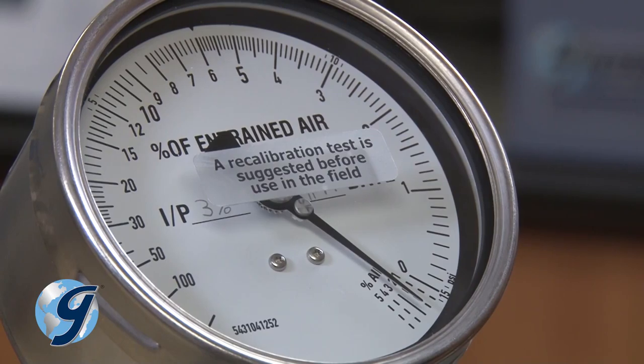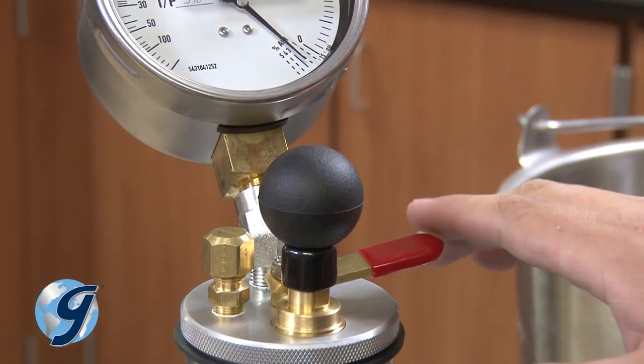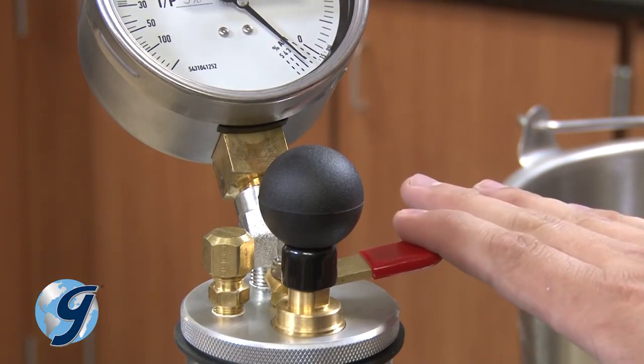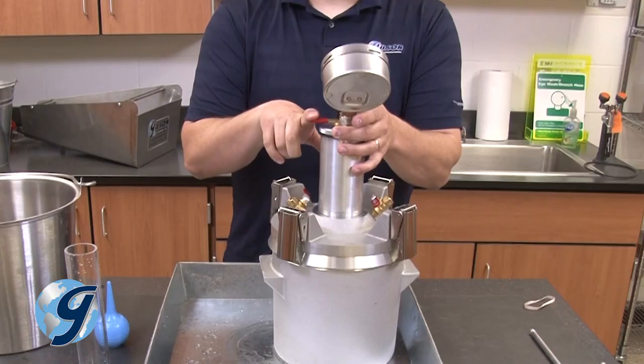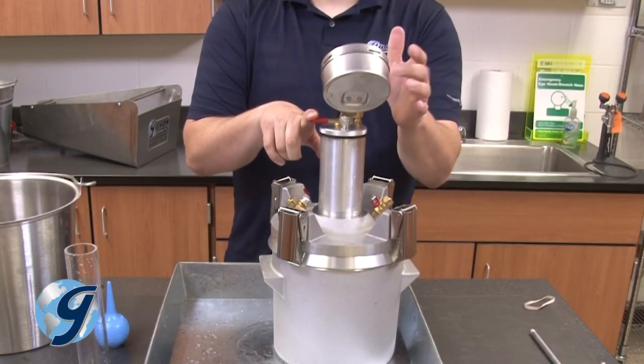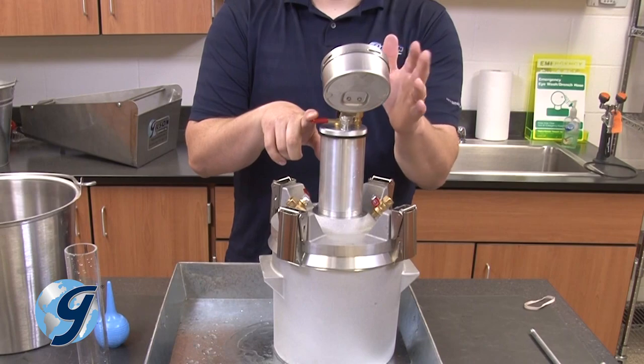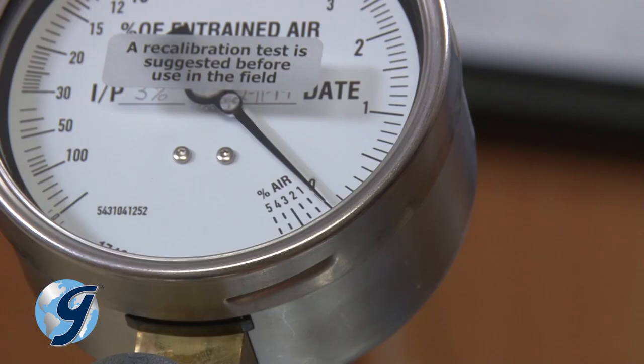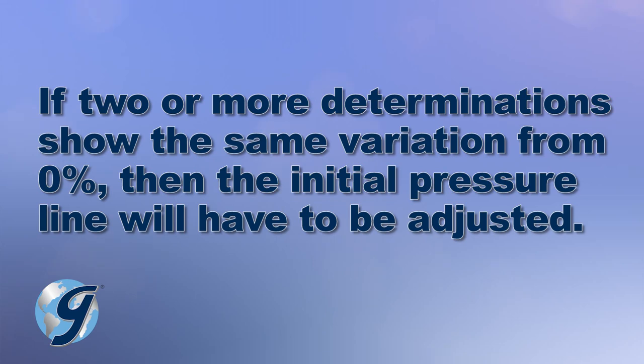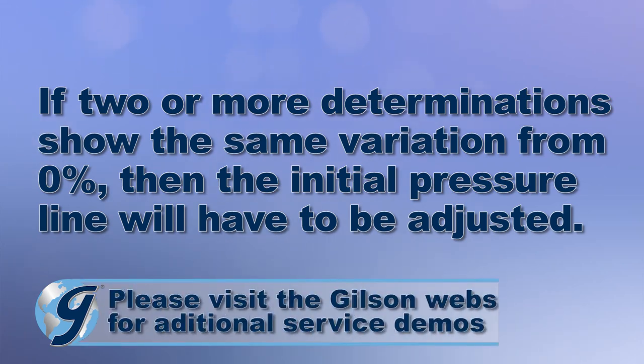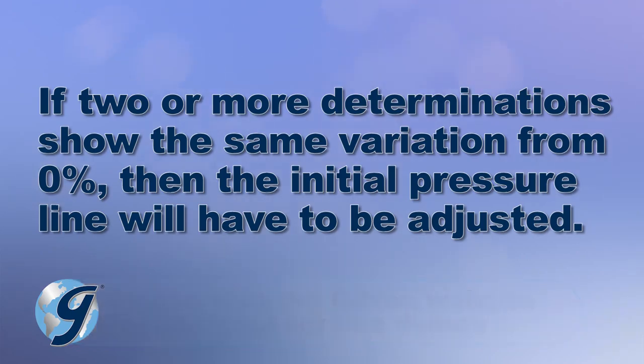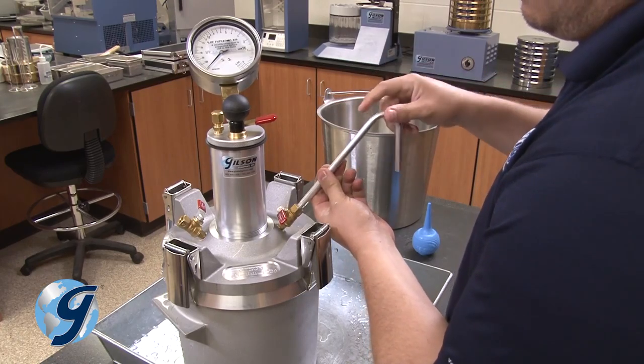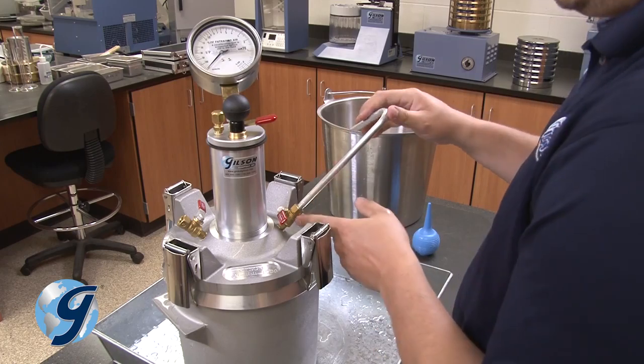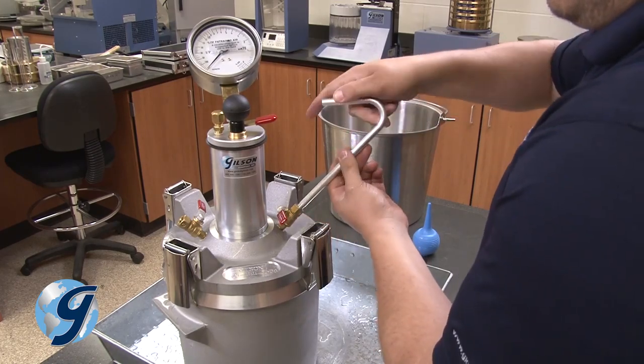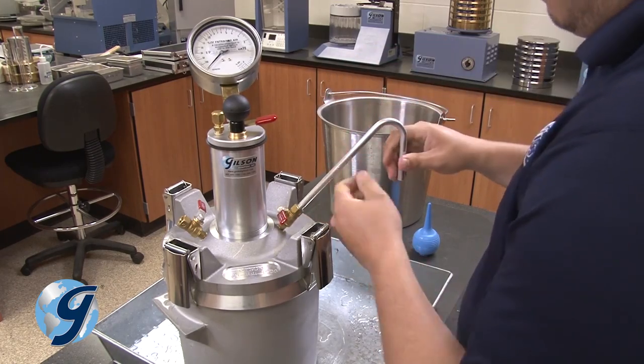When the gauge at the outset reads the predetermined initial pressure, press down on the needle valve lever to inject the air into the base. As you hold down the lever, lightly tap the gauge body again to make sure that the gauge rests on 0. If 2 or more determinations show the same variation from 0%, then the initial pressure line will have to be adjusted. Now screw the bent calibration tube into the top side of the petcock that already has the short tube fixed to it, making sure that the tube opening faces down.